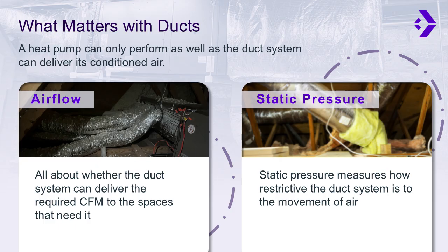Next, static pressure. Static pressure measures how restrictive the duct system is to the movement of air. Undersized trunks, bad transitions, restrictive filters, and long duct runs can all increase static pressure. When static pressure rises, the delivered airflow drops, forcing the fan to work harder and reducing the system's efficiency. This is why duct sizing is so important.